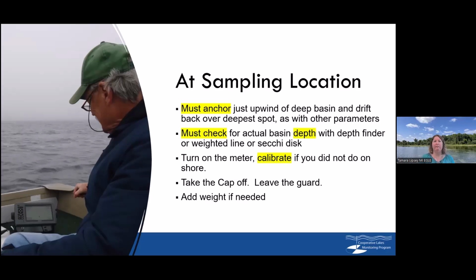Take that cap off. Sometimes people just forget that the cap needs to come off. The actual probe is in that cap. The purpose of the cap is just to protect it. So make sure you take off that cap, but leave on that metal guard. That metal guard protects that membrane, and the membrane will get damaged if you try to sample without the guard. And then you can add that little weight if needed to make sure you're keeping your cable straight.